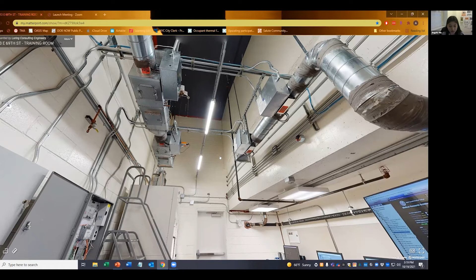This room was built to simulate a wet laboratory, one of the more complex environments on our campus. Wet labs are almost always negative pressure, a concept that's new to most onboarding staff. To simulate it, we have a line of supply and exhaust ductwork, each with two sets of controllers, one for each BMS vendor on campus. These are real controllers with functioning dampers and actuator components, connected to BMS panels in the room.